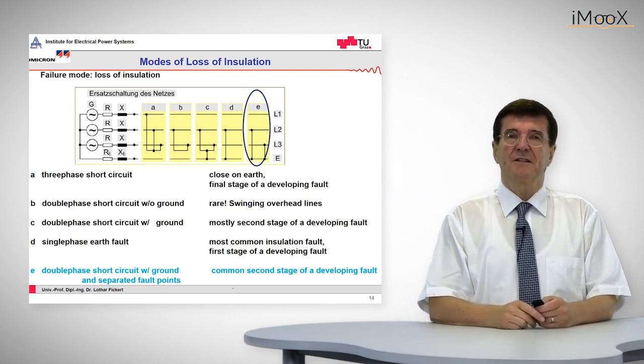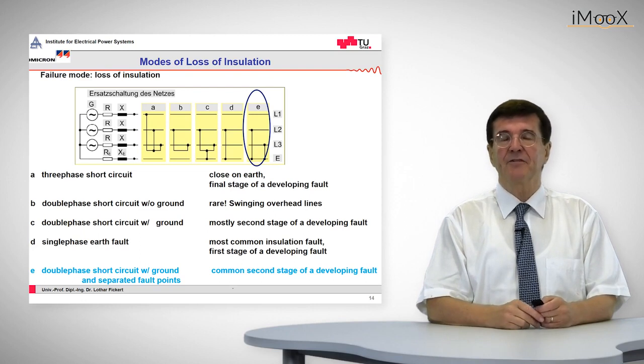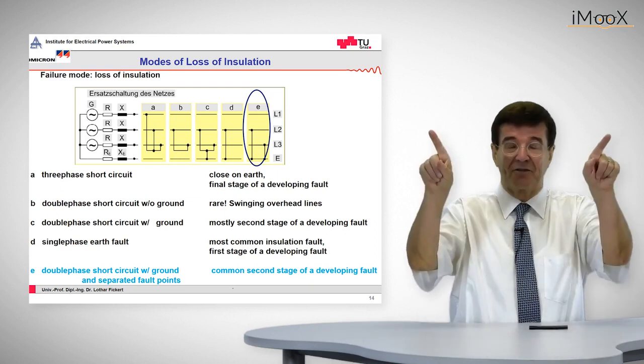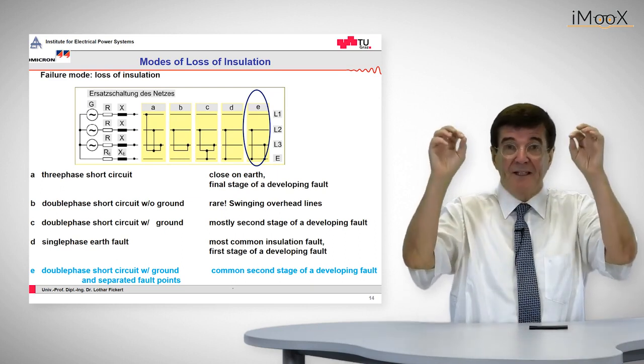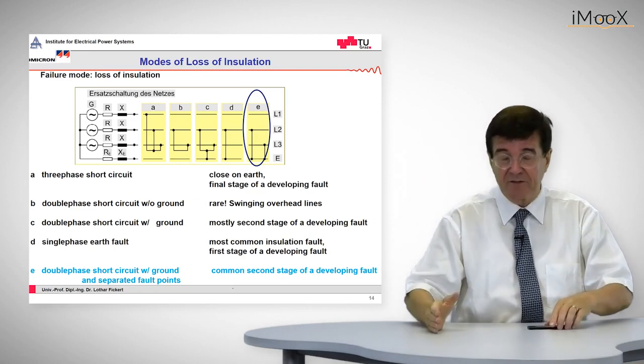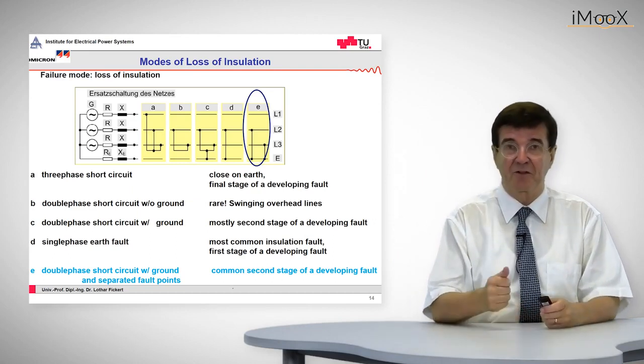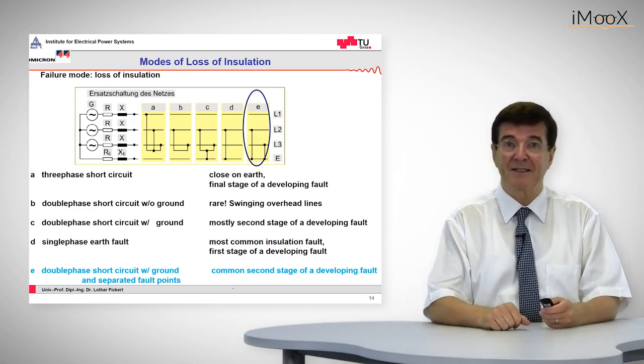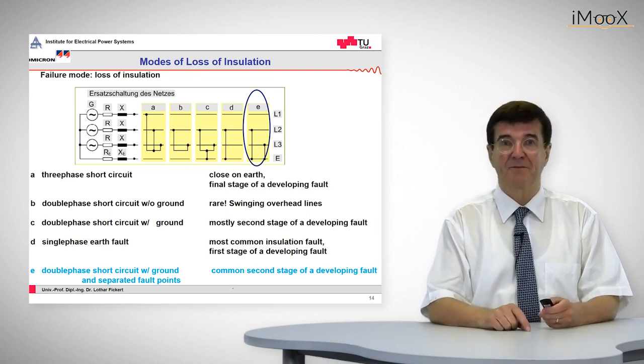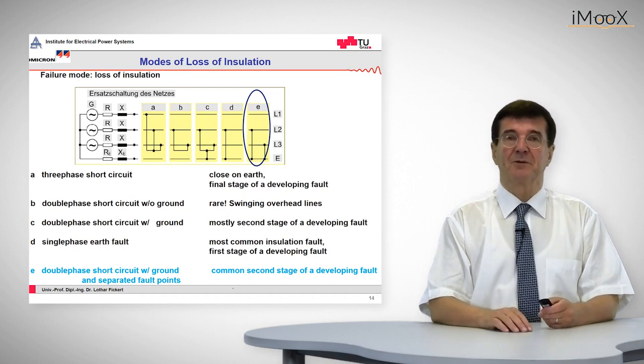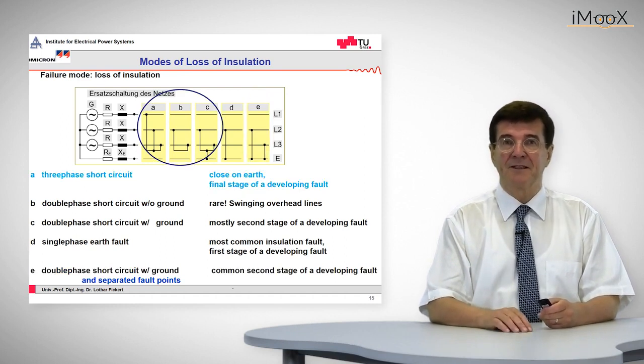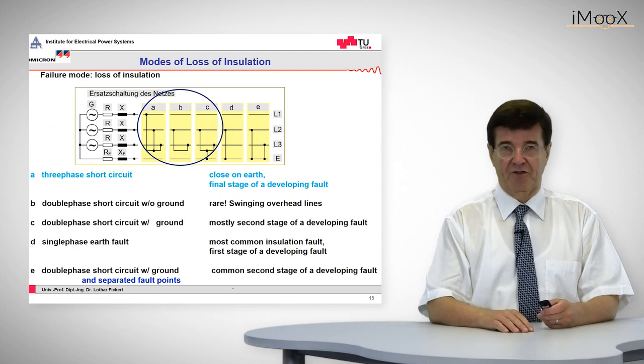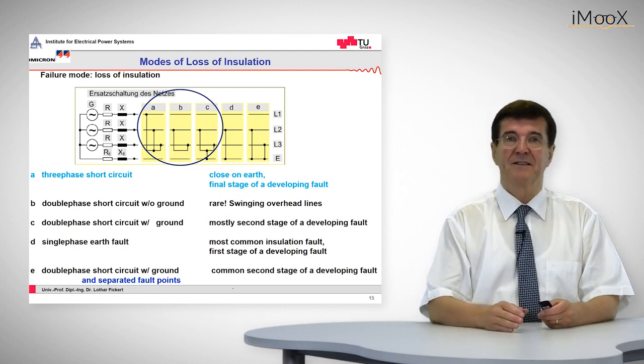This situation occurs in many cases in the aftermath of a single phase to ground fault, where due to the increase of the voltages in the healthy phases, in one of these healthy phases we have another voltage breakdown and we have a second fault point in the grid at some other place and in the second phase. So this is called the cross-country fault. In overcurrent protection I would like to deal now with the typical short circuits, that is phase to phase, between three phases and so on.